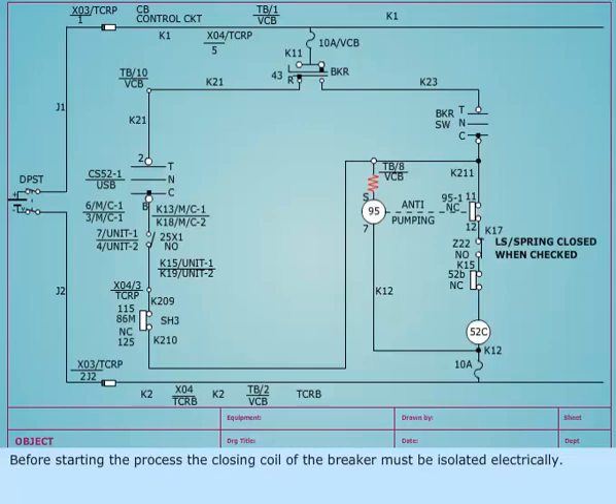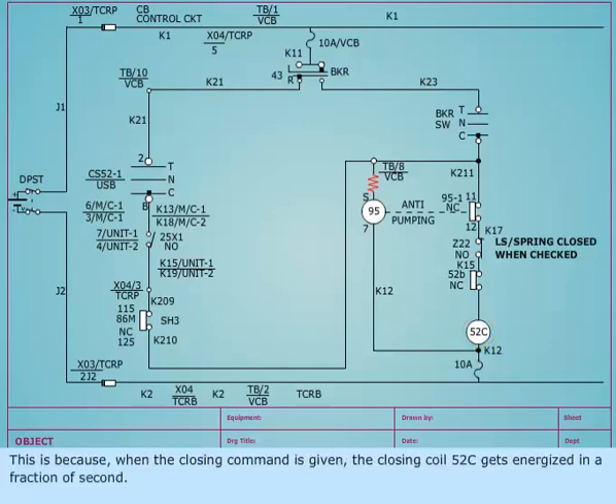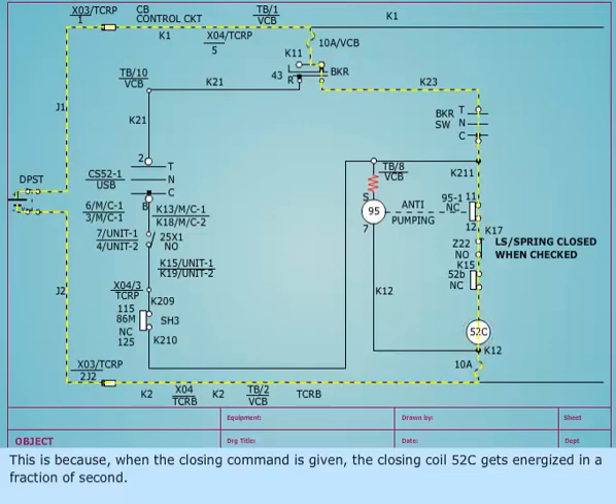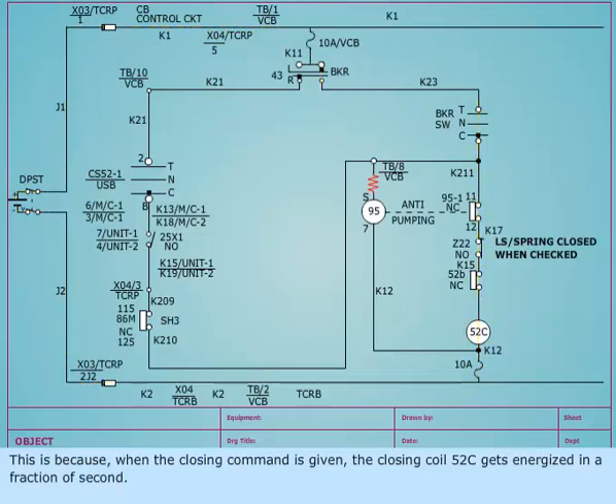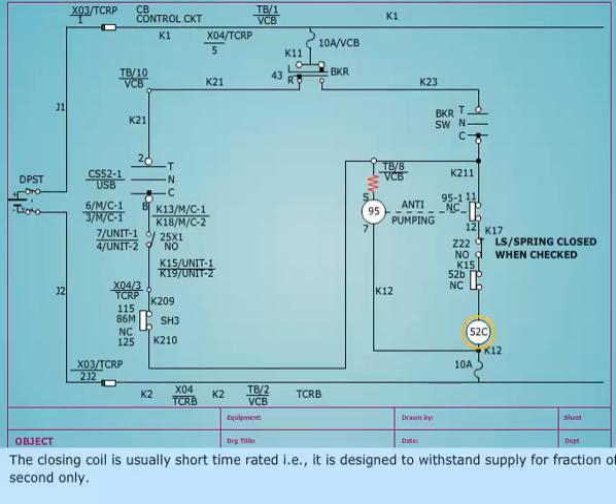Before starting the process, the closing coil of the breaker must be isolated electrically. This is because when the closing command is given, the closing coil 52C gets energized in a fraction of a second. The closing coil is usually short time rated, that is, it is designed to withstand supply for fraction of a second only.